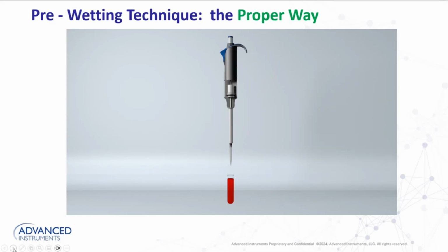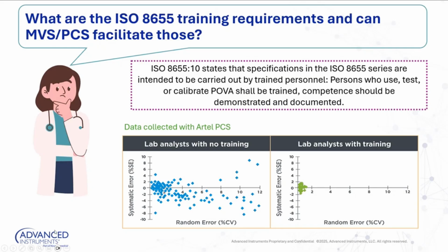Now, when it comes to ISO 8655, they recommend that you do that 5 times. And then they recommend that you take 5 replicates. And then they recommend that you put on a new tip and you pre-wet 5 times and take 5 replicates. That's what your 10 data point single volume calibration process would look like. So some of you, I hope, have a good takeaway from this particular slide. So let's talk a little bit more about 8655 and the training requirements.